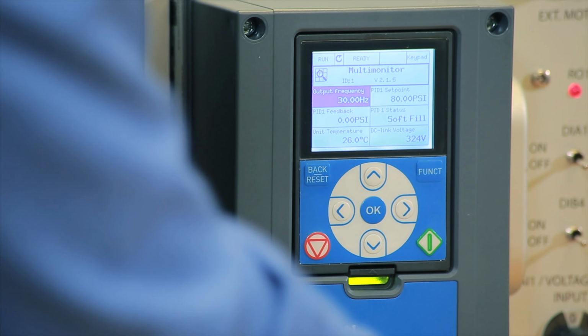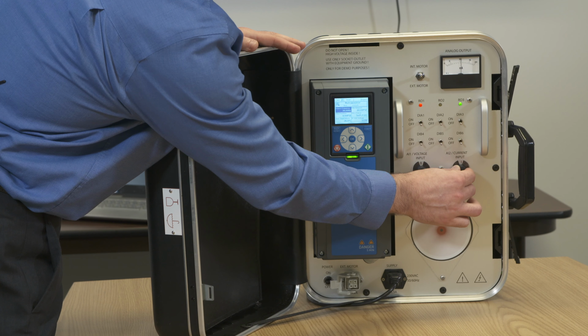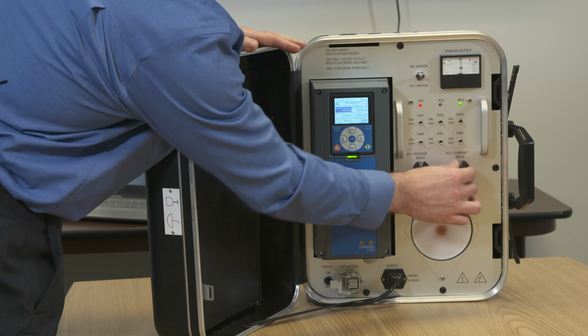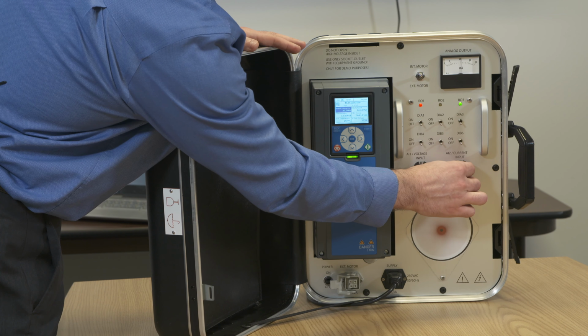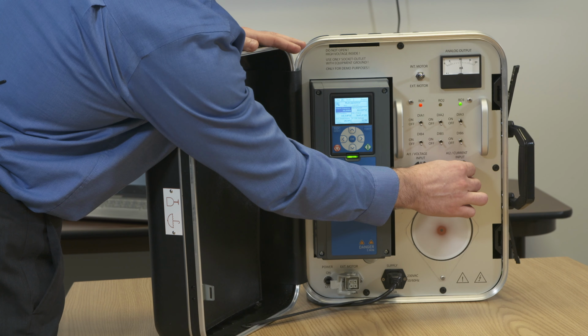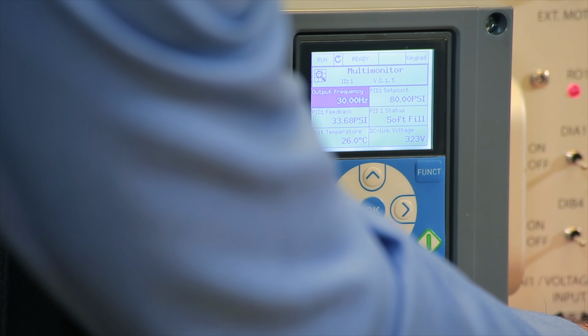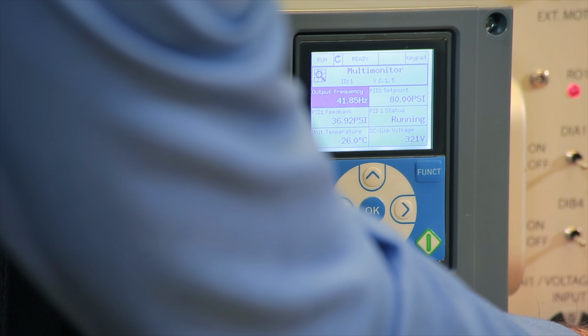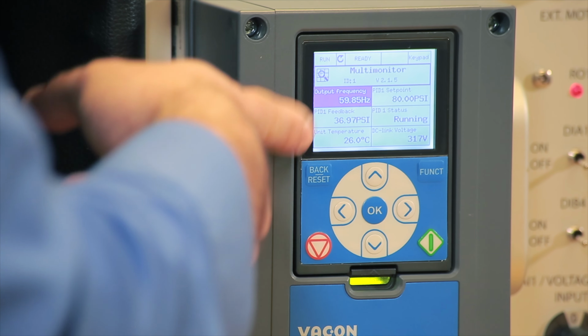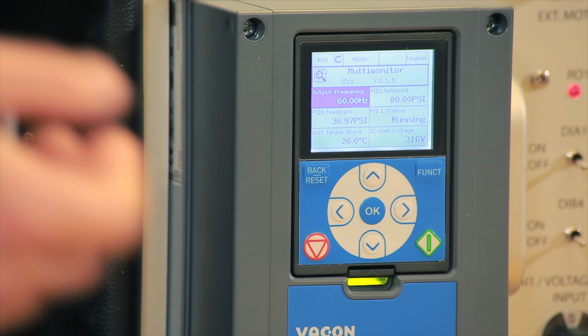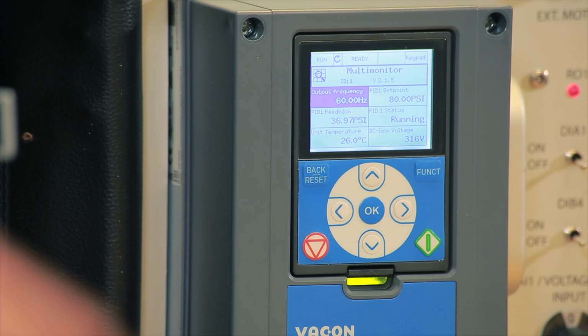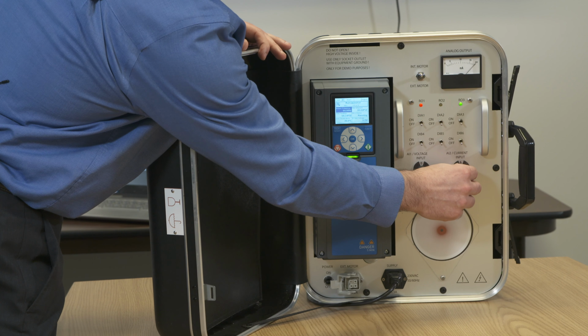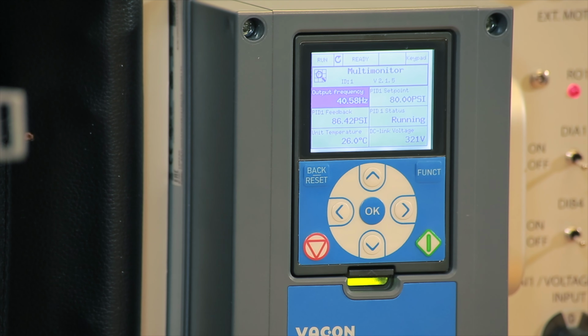Everything is done automatically. We're going to increase the pressure and monitor this second value here until we get to 35, and after that the speed should increase to 60. Here we go. We're above 35 psi. We've gone to 60 hertz because now the pipes are pre-filled, they're safe, there's no water hammer. Let's ramp up. And then once we go above 80 psi, the drive will slow down and it's going to go to sleep eventually.